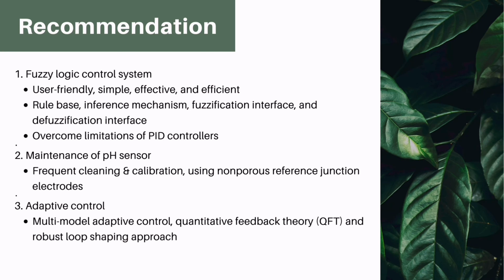The application of fuzzy control solves all the non-linearity issue by overcoming limitations of PID controllers. The second recommendation is by maintenance of pH sensor. Frequent cleaning and calibration using non-porous reference junction electrodes could eliminate most of the pH sensor problems. The third recommendation is adaptive control. Adaptive controls can be used to solve problems other than non-linearity. Examples include the multi-model adaptive control, the quantitative feedback theory QFT, and the robust loop shaping approach. All the controls mentioned seem to be effective at resolving the disturbance control issue.